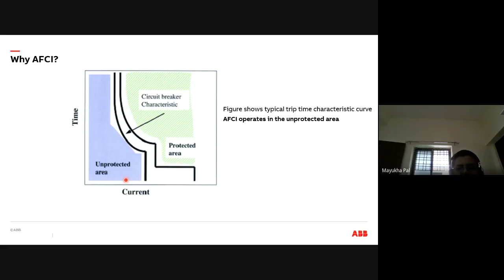Typically, if you look at a trip time characteristic curve for a circuit breaker, this is how it looks. You see the protected area, where the circuit breaker performance is this trip time characteristic. Now the AFCI runs in the unprotected area. The way these signals are, that's where it is critical. So understanding arc physics is a big deal, and we have a lot of research on that, and it's getting mature, and certainly we are able to detect nicely. But there is a lot of effort there as well. So this protects the unprotected area of your trip time curve.